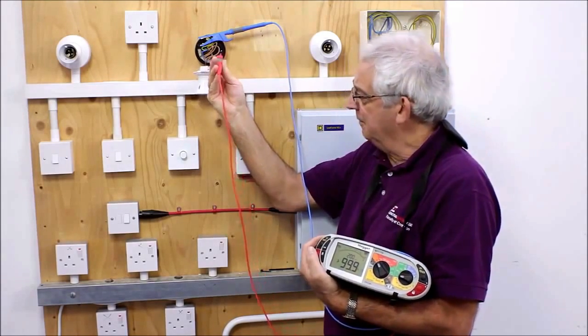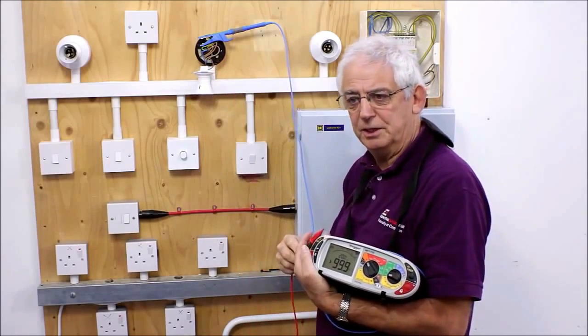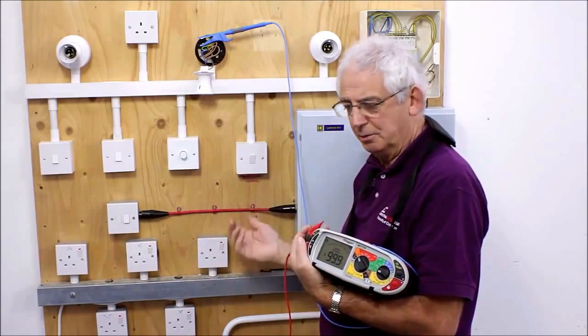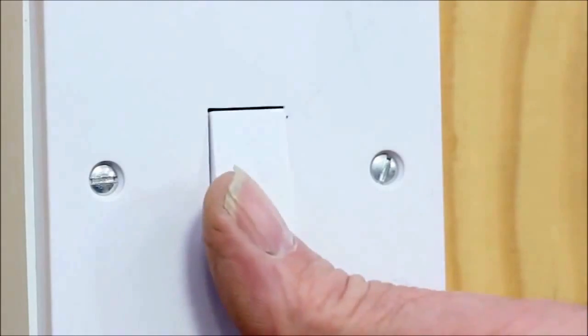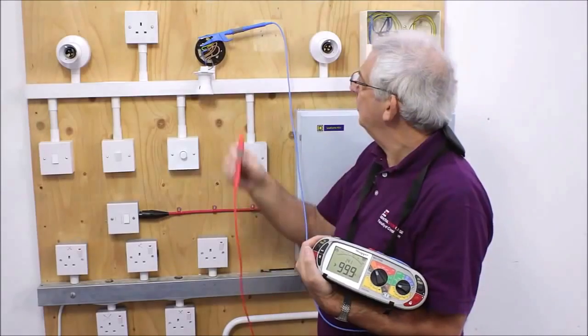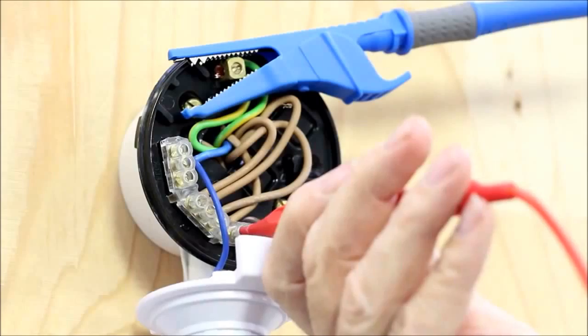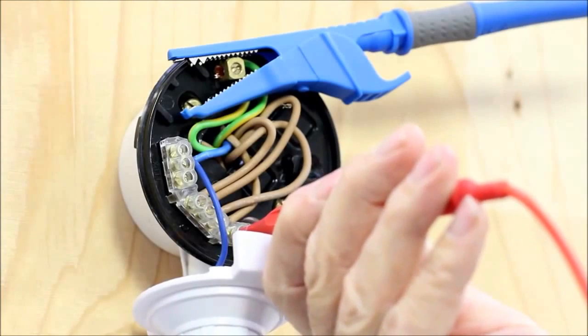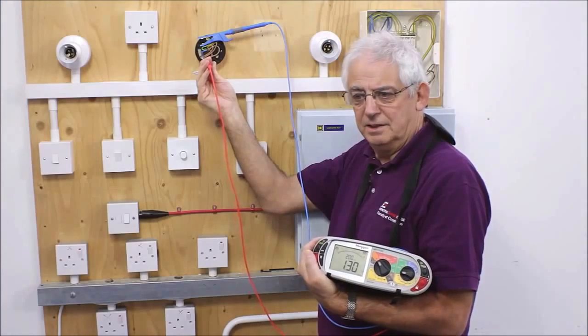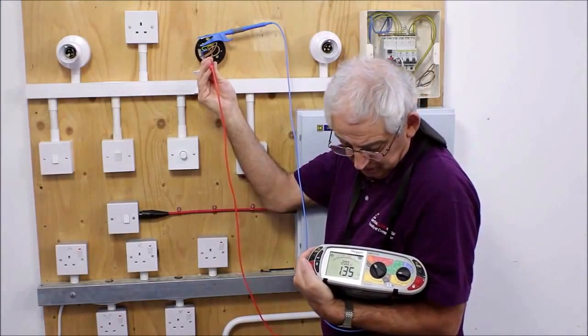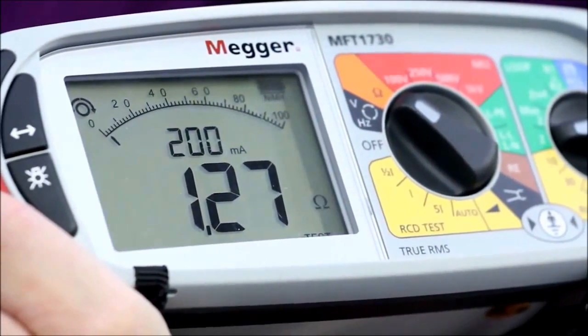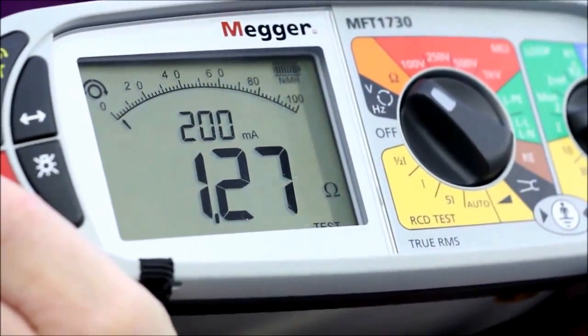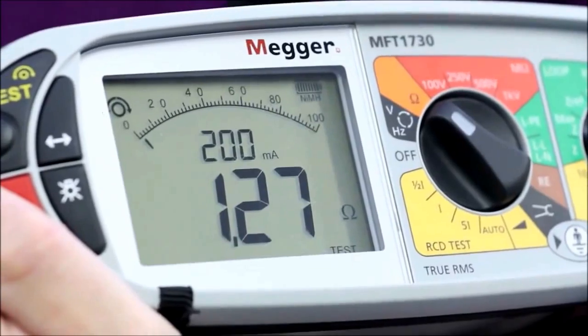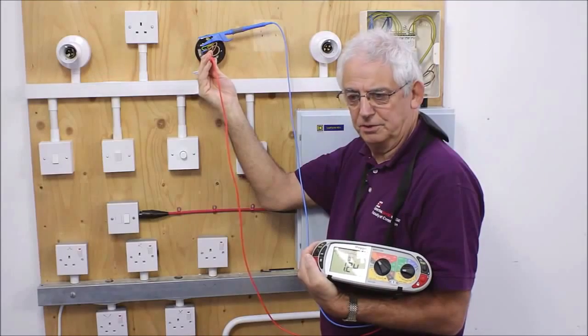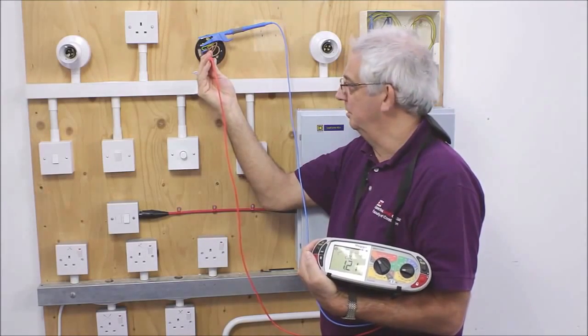The way to check it is I now need to go to the switch, turn the switch on, and then repeat the operation. If I place my probe on the switch return again, I should get a much lower reading, and the value I'm getting there, as you can see, is 1.27, and that would be the value that I'd write down for my R1 and R2 of the circuit, providing, of course, this test was carried out on the furthest point.